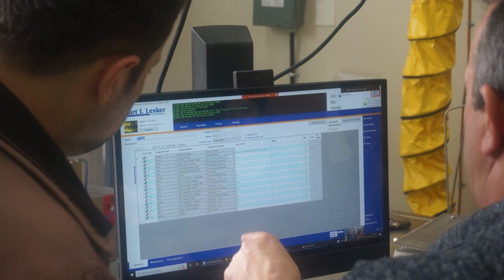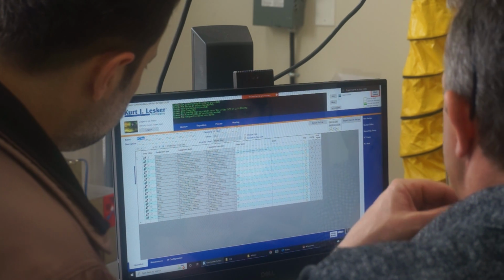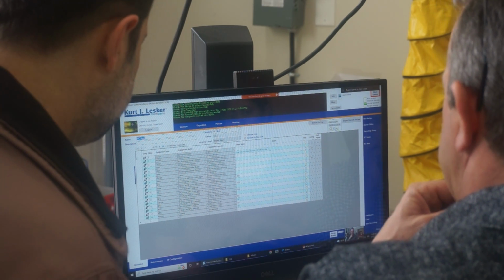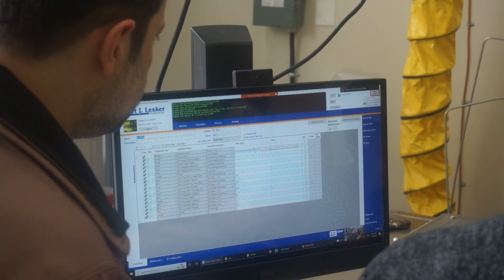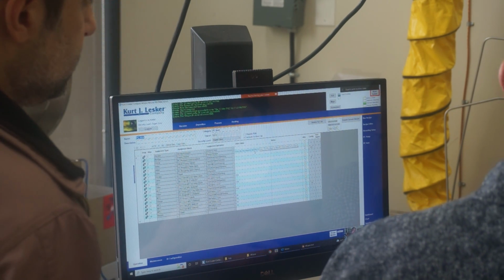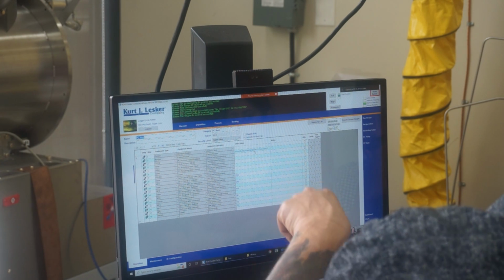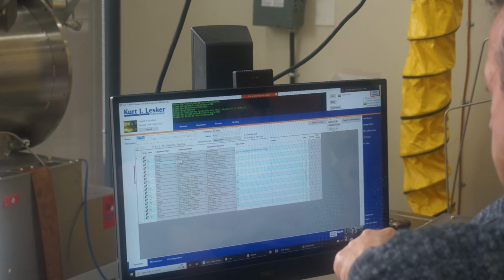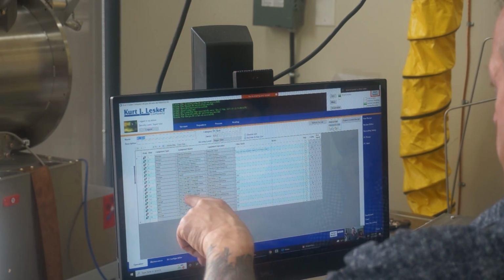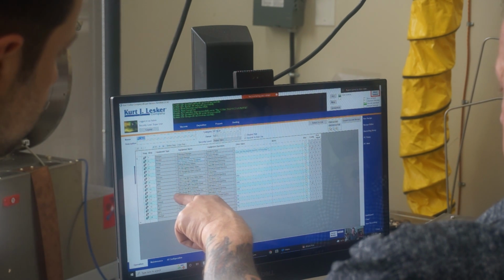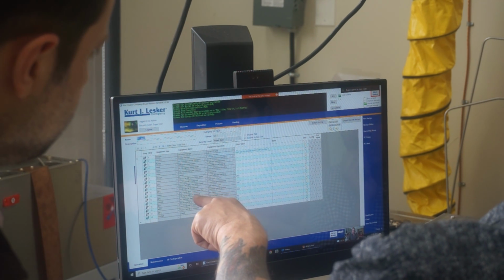Then we put a pause step in here, which you can do saying, do you want the operator to do something? Do you want them to check something? So that's this pause step, which we'll see. Then the third step, it asks if the pump is enabled.